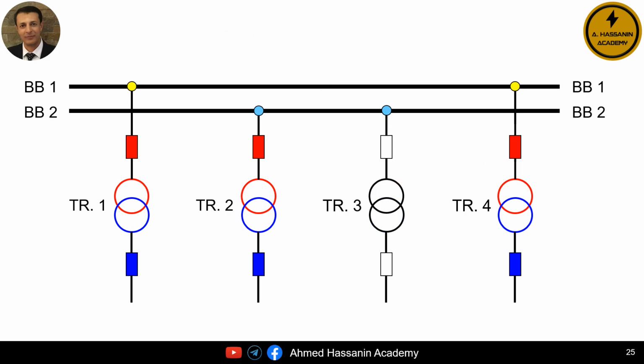The second point, as we can see in front of us, is that if we assume that transformers number 1, 2, and 4 are energized and in service, and transformer number 3 is disconnected, then it is required to connect transformer number 3. Of course, transformers number 2 and 3 are connected to the same distribution bus bar number 2, and therefore we will notice that when transformer number 3 is energized, a magnetizing inrush current may occur in transformer number 3, as we all know.